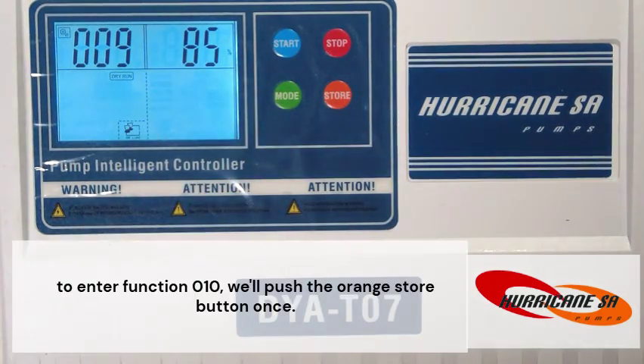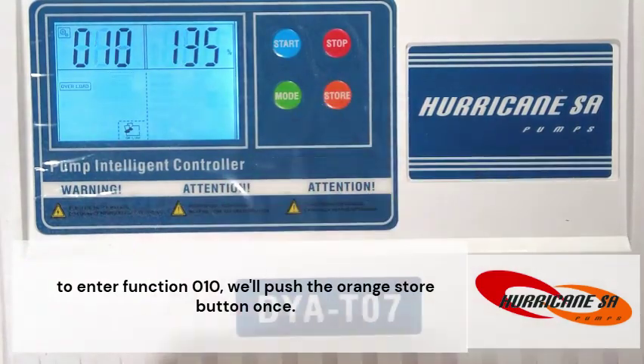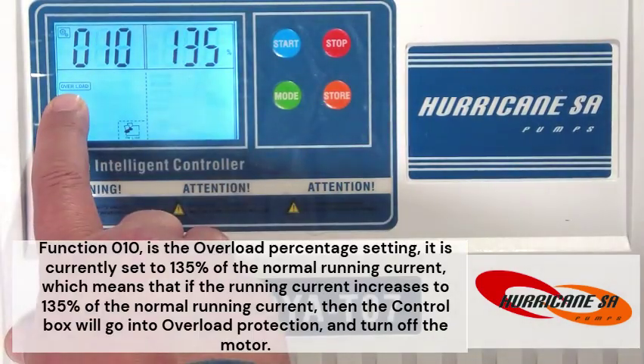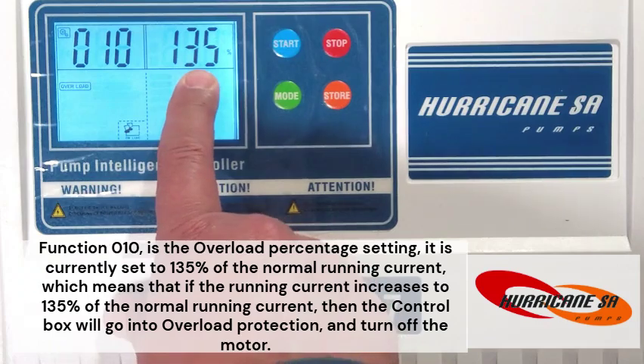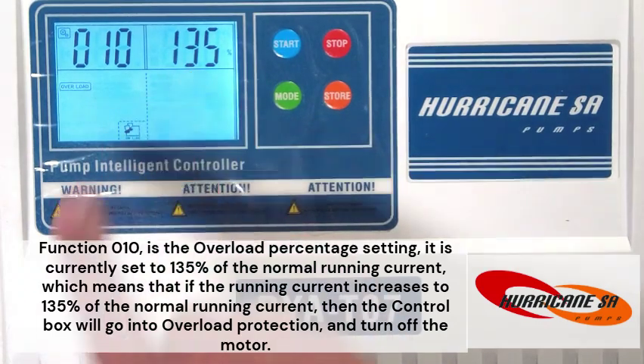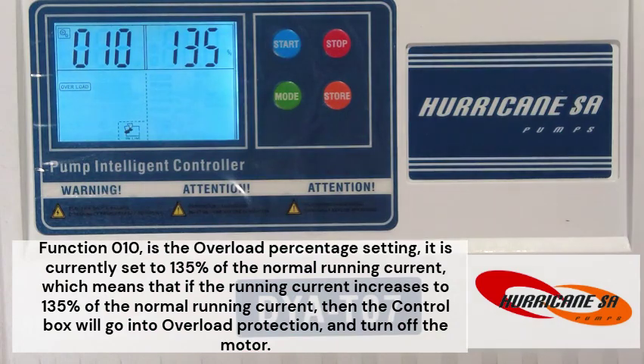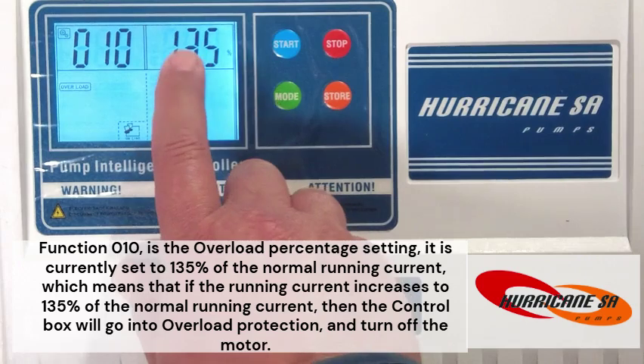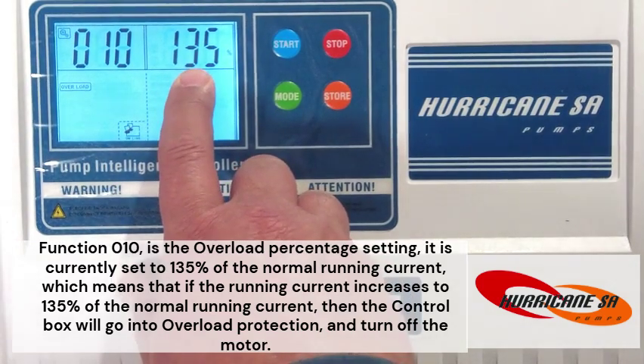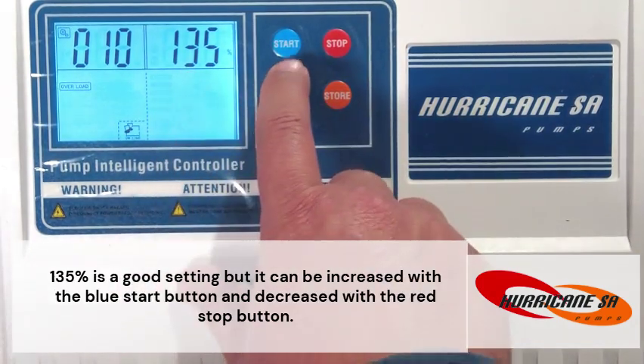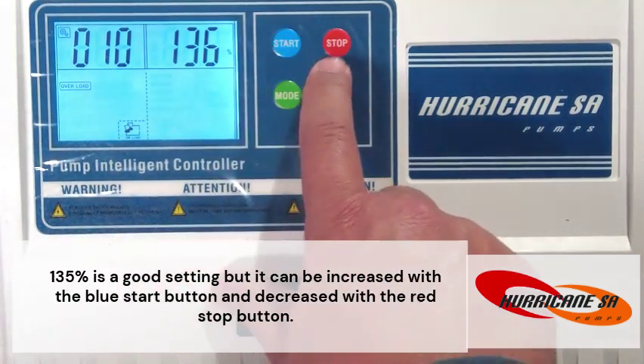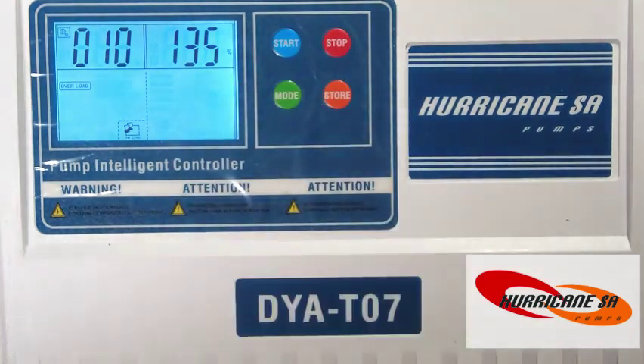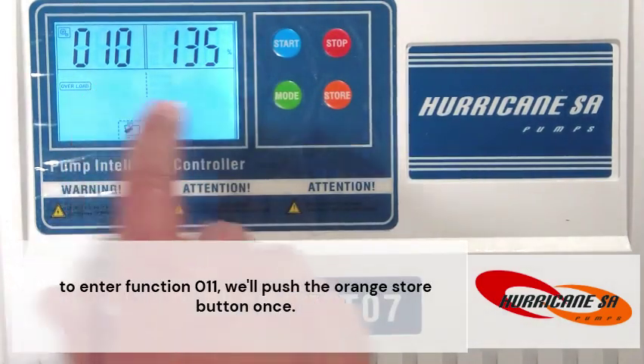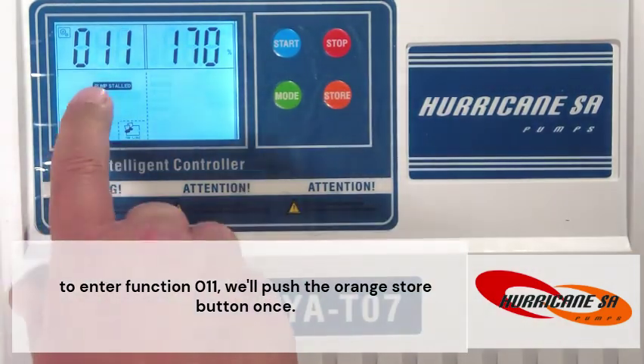To enter function 010, we'll push the orange store button once. Function 010 is the overload percentage setting. It is currently set to 135% of the normal running current, which means that if the running current increases to 135% of the normal running current, then the control box will go into overload protection and turn off the motor. 135% is a good setting, but it can be increased with the blue start button and decreased with the red stop button.